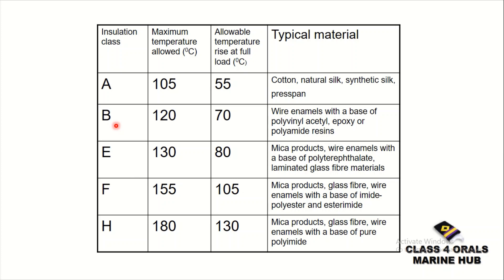Next comes Class B insulation. The maximum temperature allowed is 120 degrees centigrade, with a full load allowable temperature rise of 70 degrees centigrade. The material for this class is wire enamels with a base of polyvinyl, acetyl, epoxy, or polyamide resins.